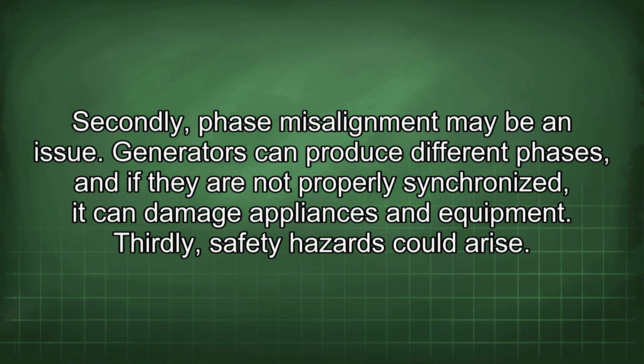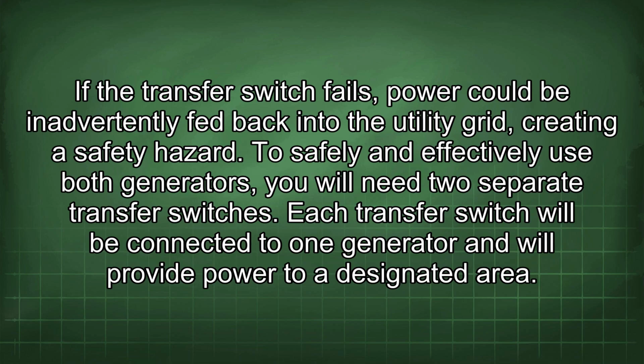Thirdly, safety hazards could arise. If the transfer switch fails, power could be inadvertently fed back into the utility grid, creating a safety hazard. To safely and effectively use both generators, you will need two separate transfer switches. Each transfer switch will be connected to one generator and will provide power to a designated area.